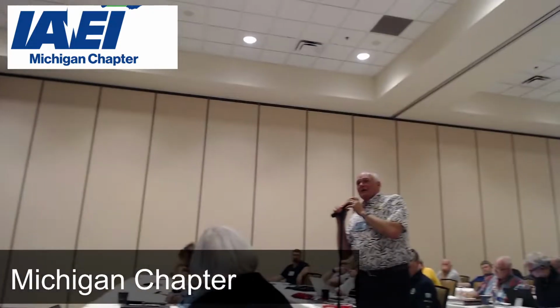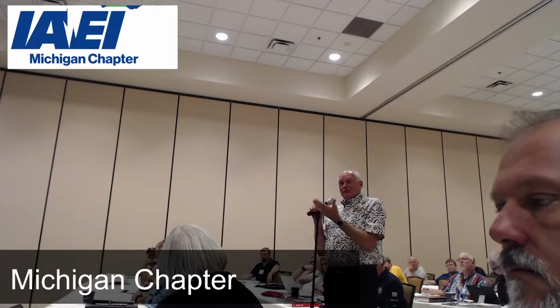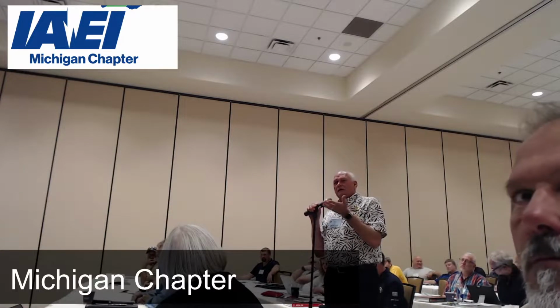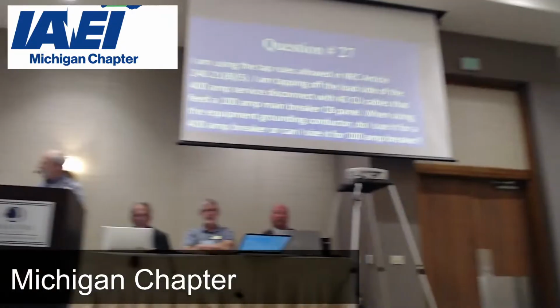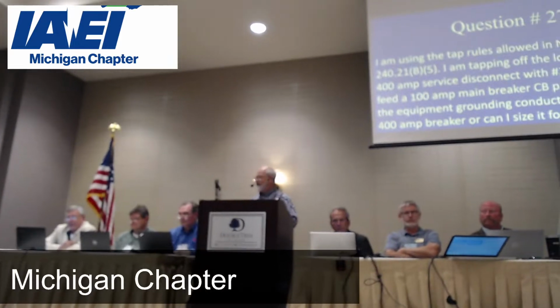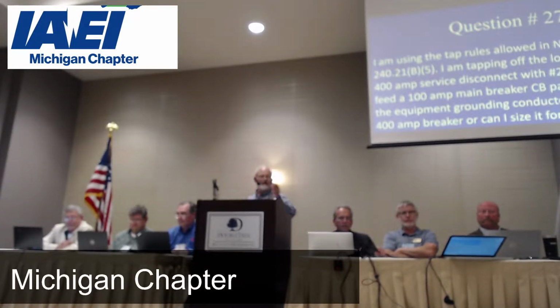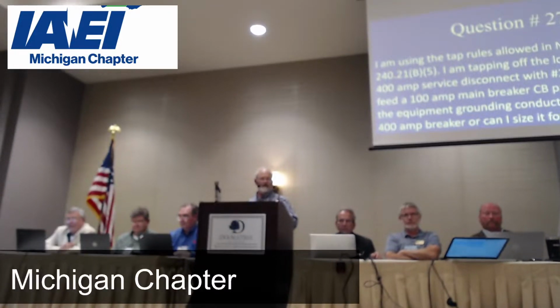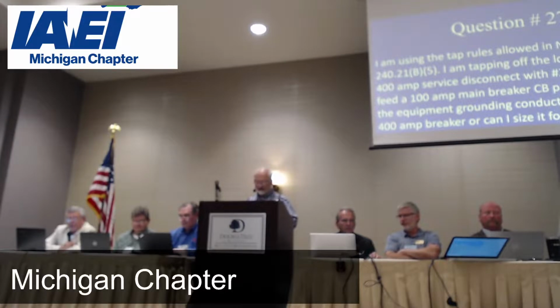And now Dave's getting up here. Now I'm in trouble. Testing, there it is. When you reference the circuit, they don't have to be any larger than the circuit conductors. Again, these aren't circuit conductors, so maybe that's something that might need to be looked at. Yeah, that's a good thought. And even as I was saying it, I was thinking, well, which of the circuit conductors? The large conductor you're tapping off of, or the smaller tap conductor? The fault is going to be carried on the smaller conductors. That may be a good subject for a little code change clarification for 2026.